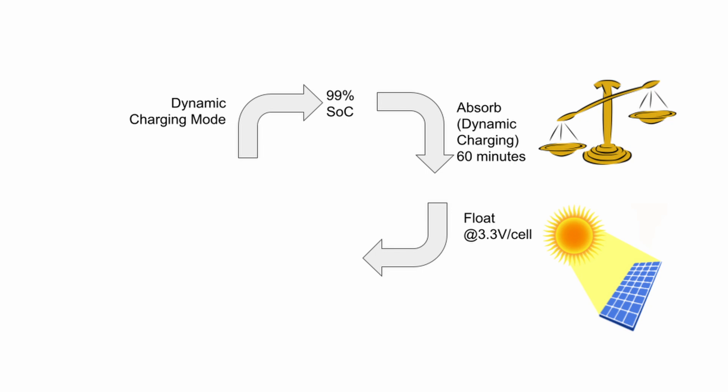If we were to tell the charger to fully stop rather than floating, you could get the scenario where a solar inverter during daylight is told to stop. This could then prevent it from powering the house loads directly from the sun and causing the battery to begin discharging. Not really an ideal solution. The float mode defaults to six hours, but you can increase or decrease this in the settings.